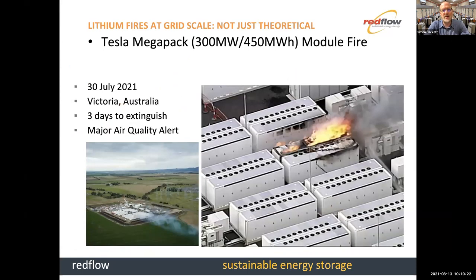An interesting example of that happened literally just two weeks ago here in Australia, in Victoria. On the 30th of July, a large Tesla-based Megapack system, a 300 megawatt system, had one of its main battery containers catch fire during commissioning testing. As an impressive example of how hard it can be to put these fires out, it took three days to extinguish the fire, and led to major air quality alerts across big chunks of Melbourne, because when these things burn, the smoke involved is not something you really want to breathe in. A big chunk of Melbourne was literally told to close their doors and not leave home for a while.